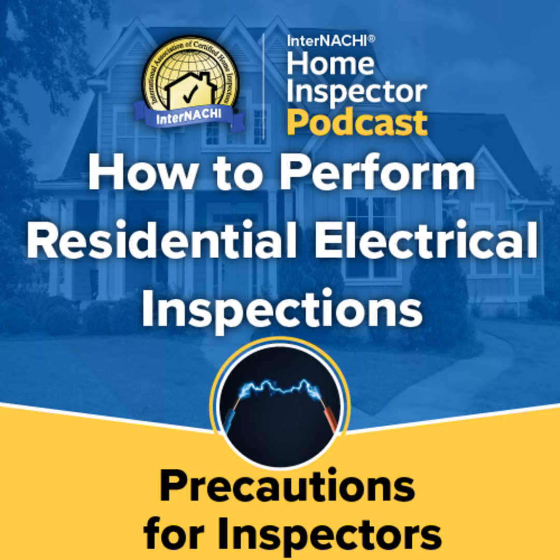Precautions for inspectors: first, assess your risk tolerance. You are not required to perform an invasive electrical inspection. Removing the dead front of the electrical panel board exceeds InterNACHI's standards of practice. Even if a home inspector is highly confident of their technical training and the situation, and can confirm that the system is de-energized, any suspected problems requiring an invasive inspection should be disclaimed and deferred to a licensed electrical contractor.